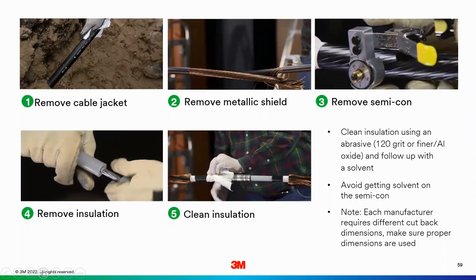So, the first thing, just basic steps, is jacket removal. Then you're going to remove the metallic shield, whether that's the tape shield or the neutral wires there on a JCN cable. But then the semicon removal, this is a very important step because as you'll see here in the next few slides, as I go over some of the failures, 90% of cable failures happen at this step, the semicon removal. So using a specialty tool in that case is nice because you can set the gauge of your blade to score that semicon the appropriate depth, and use it over and over again.